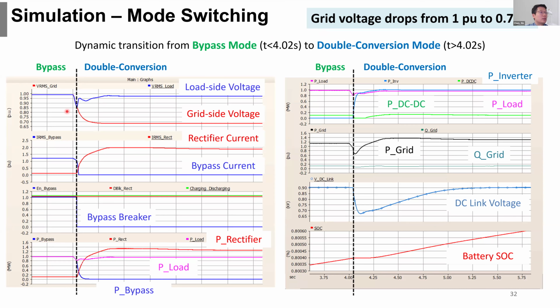We can see that this figure is the voltage. The blue curve here is the load side voltage. The red curve is the grid side voltage. We can see the grid side voltage drops from 1 per unit to 0.7 per unit. And at this point, we have a mode switching from the bypass to double conversion. And during this event, we can see the load side voltage is still maintained at close to 1 per unit, even though the grid side voltage dropped to 0.7, because we have switched to the double conversion mode. So here, the second figure is the current. We can see the bypass current is jumping to 0 and the rectifier current increased to 2 per unit. That means the rectifier and inverter is picking up the load.